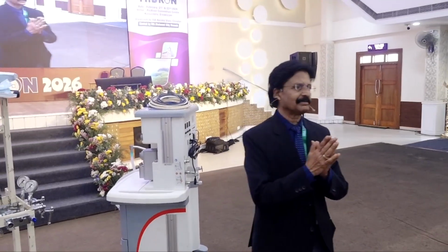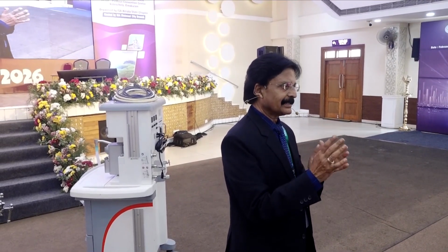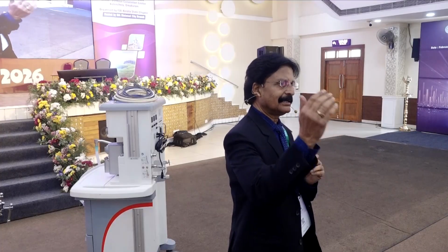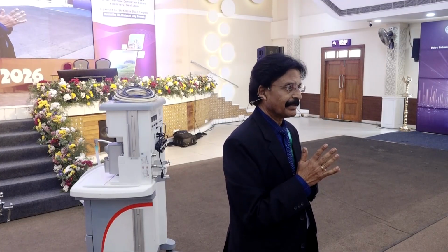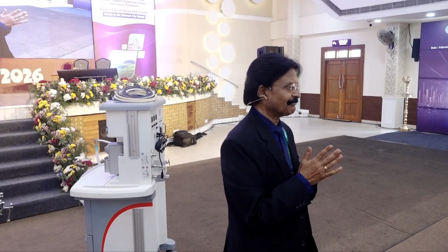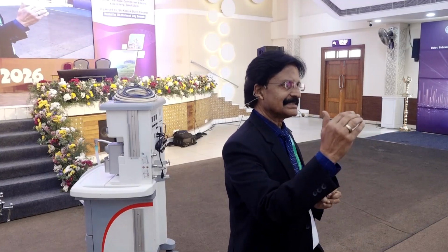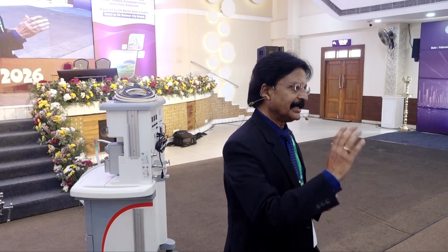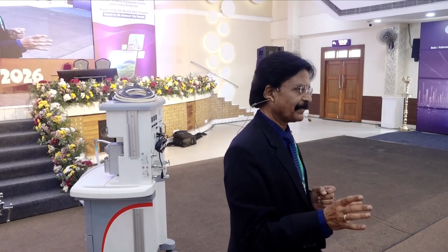Then the other important thing I was telling you is the fail-safe valves. The fail-safe valves are there in between the pressure regulator and the flow control valves. And there are two types of fail-safe valves in the Draeger type of machine and GE. So this is almost like a GE machine only. In a GE machine, it is called a shut-off valve. So if the oxygen pressure drops to less than 30 pounds per square inch, it shuts off nitrous oxide. You cannot just use nitrous oxide. It is called a shut-off valve.